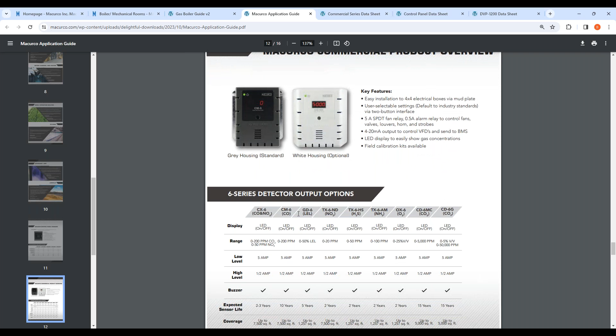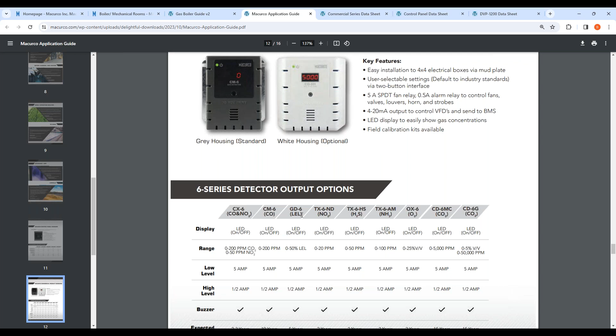Within all of our detectors, like the CX6, you'll have the nomenclature of the gas underneath it. So a CX6 is carbon monoxide and nitrogen dioxide, and you can go down the list and get a gist of everything else. The GD6, when it says LEL, is dedicated for methane, propane, or hydrogen, one of those three. The big key factor is where you mount those detectors. Methane and hydrogen rise, they're lighter than air, so they go up to the ceiling, whereas propane is heavier and goes to the floor.